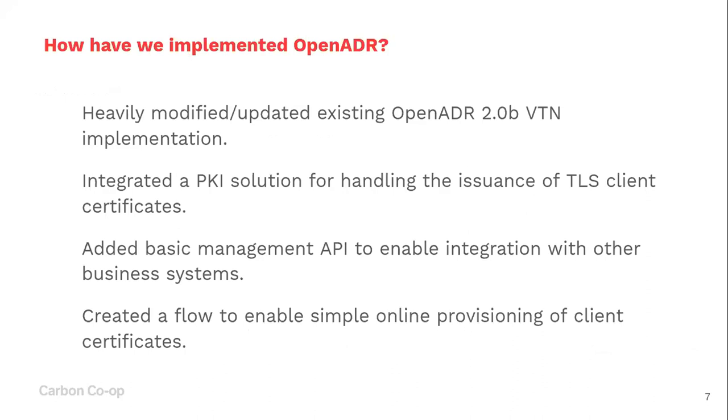In implementing this, we had to heavily modify and update an existing implementation of OpenADR, which itself has been around for quite a few years now. And we've also needed to integrate a public key infrastructure solution for handling the issuance of TLS certificates, which are required by the OpenADR standard. As well, in addition to this, we've added a management API and created a sort of process flow to enable the provisioning of the clients. These are all not necessarily things that are included in OpenADR and which you have to add on to it.